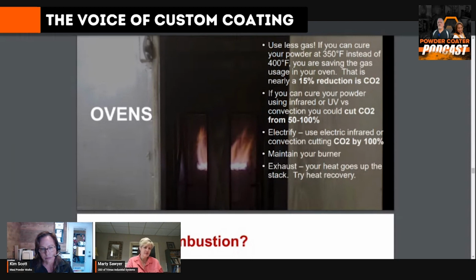Yes, that will save you money, but first of all, you could create a major safety problem for yourself if you shortcut purge. Purge is there for a reason. It's per code. Don't ever screw with it. Follow NFPA, your insurance company, everybody, you've got to do that. You can't put a VFD on a purge and turn it down and take shortcuts. It's just absolutely black and white.